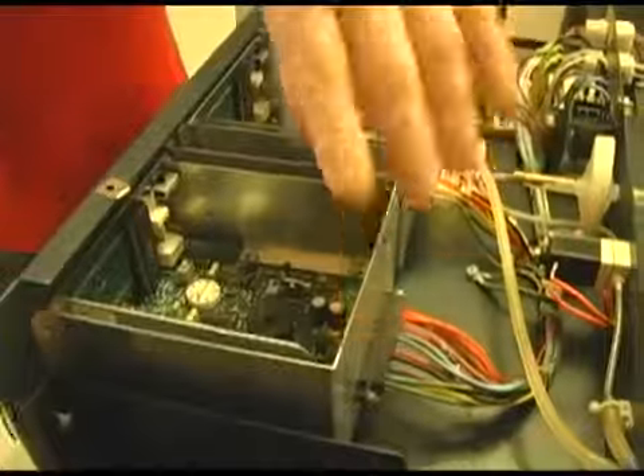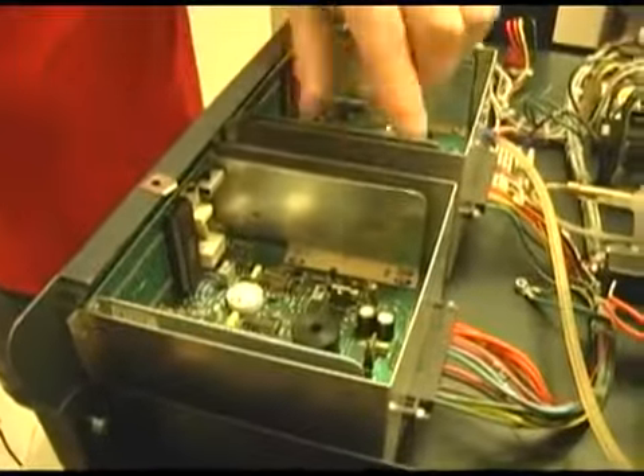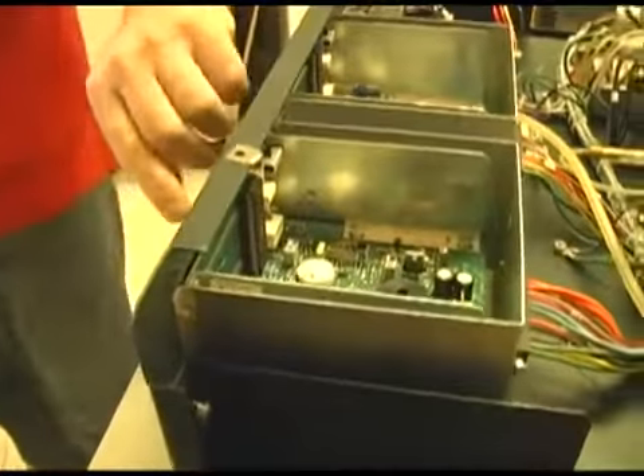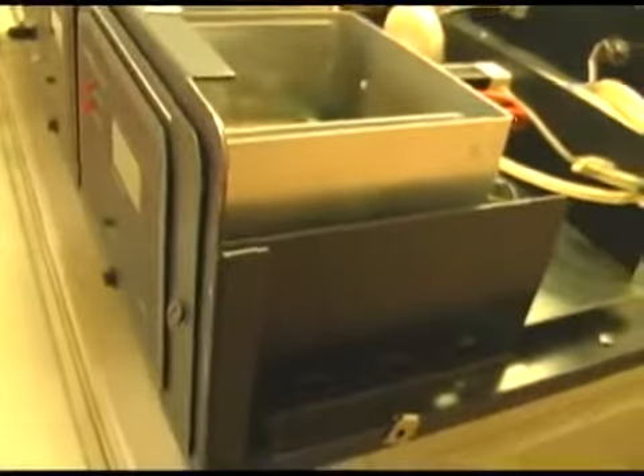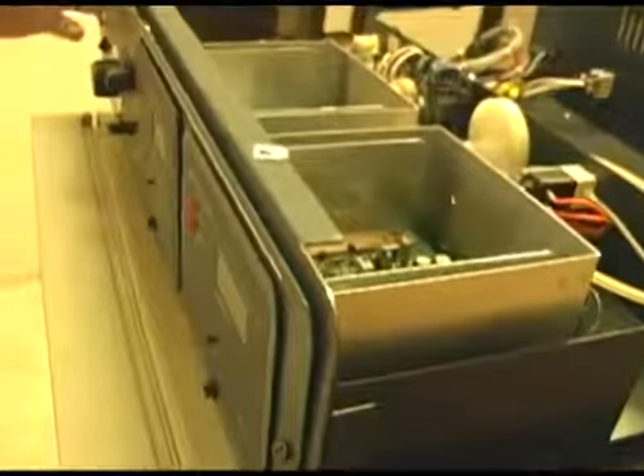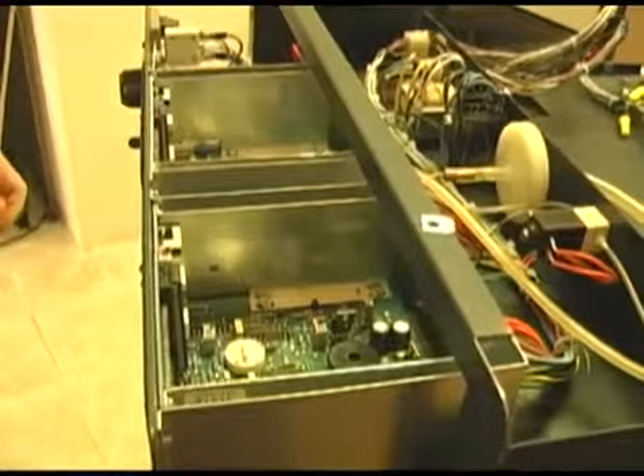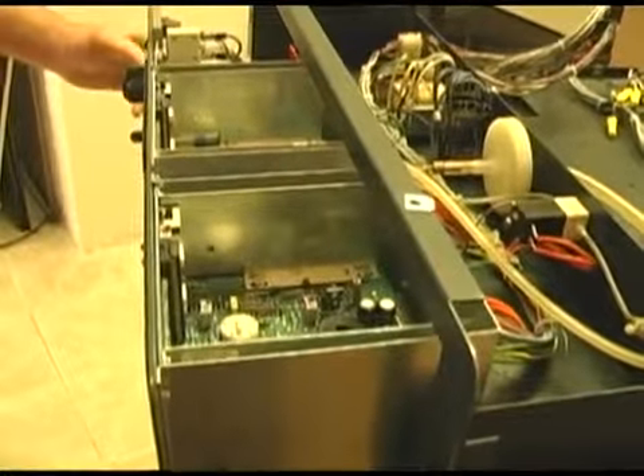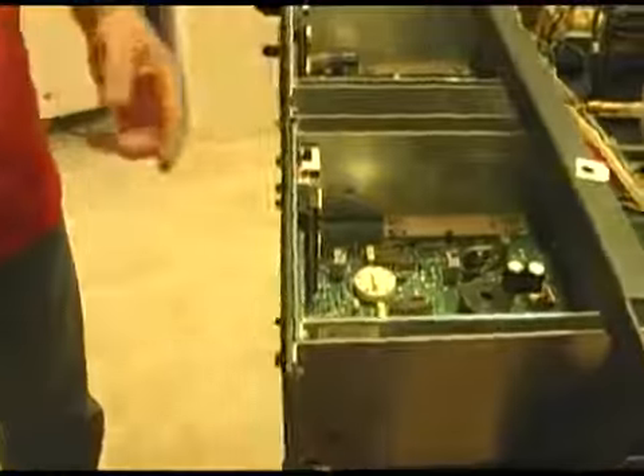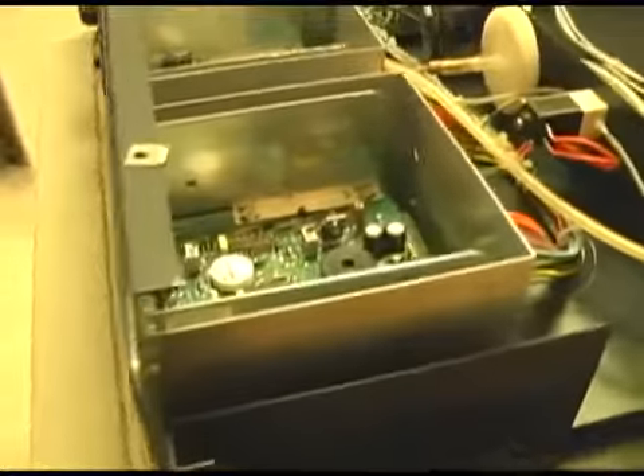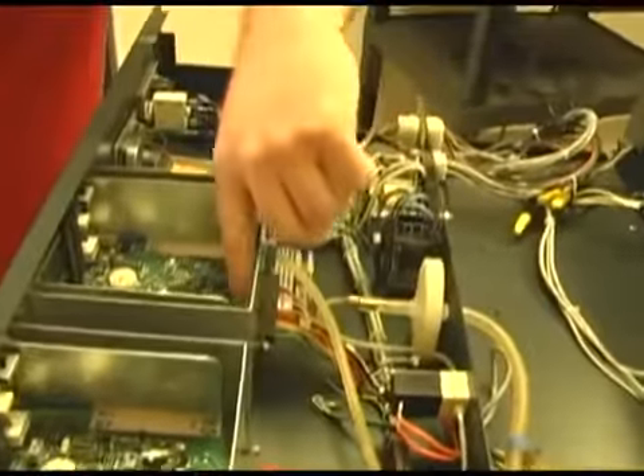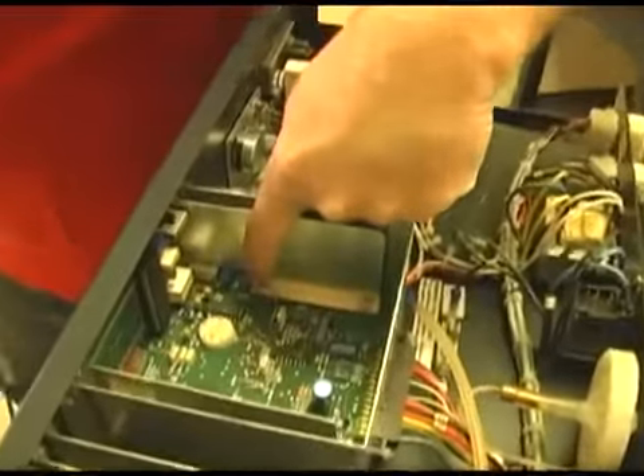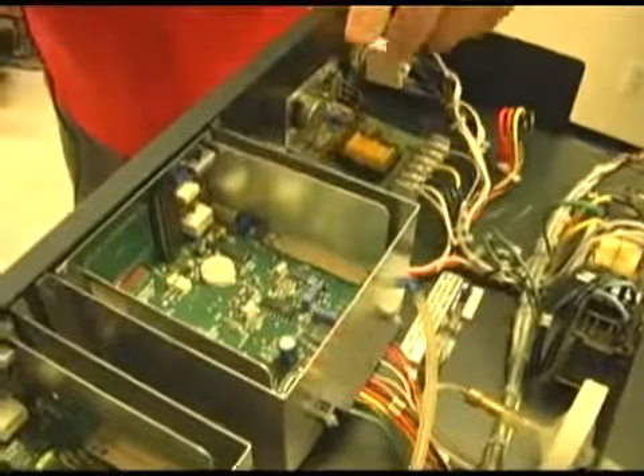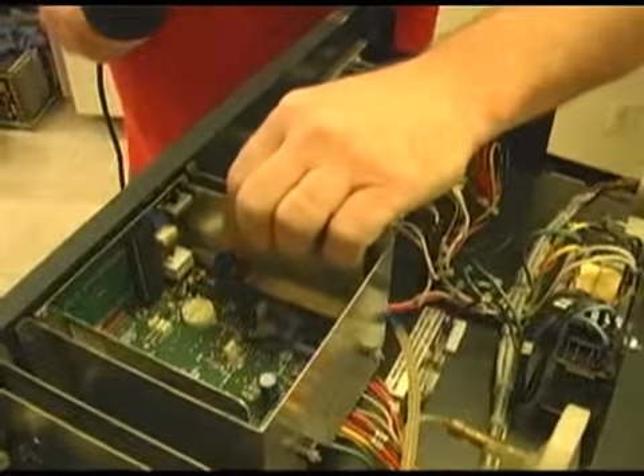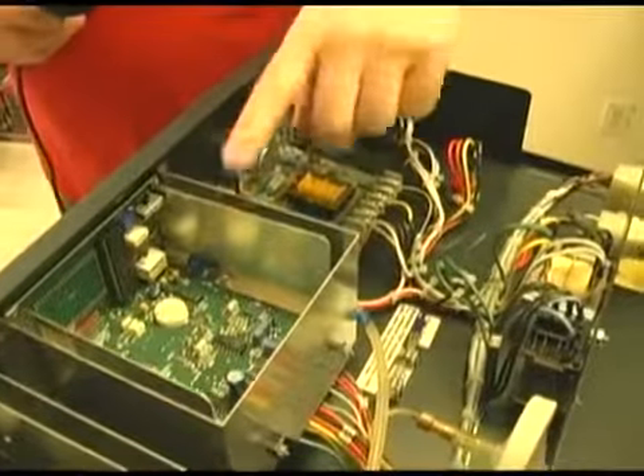Let's take a look at the electronics. Here is your monitor for your alarm. Please note that this simply pulls out. You push a button in the front of the instrument, and that whole module will come out just like a drawer comes out. That saves you from having to take the top off. And again, these pop off also and slide right out. Okay, on to the CO2 module. Again, you can see how this pulls right out, and I will point out that you've got a little pot over here that you can use to change the gain of the instrument. That's a calibration, not a set point.